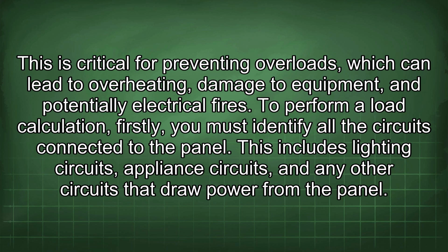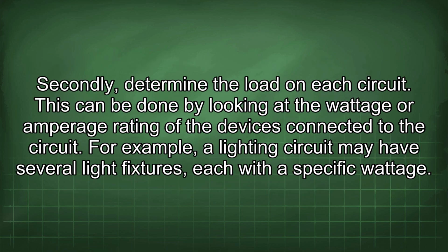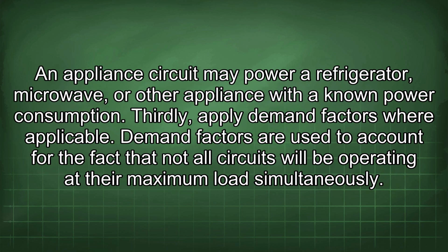This includes lighting circuits, appliance circuits, and any other circuits that draw power from the panel. Secondly, determine the load on each circuit. This can be done by looking at the wattage or amperage rating of the devices connected to the circuit. For example, a lighting circuit may have several light fixtures, each with a specific wattage. An appliance circuit may power a refrigerator, microwave, or other appliance with a known power consumption.